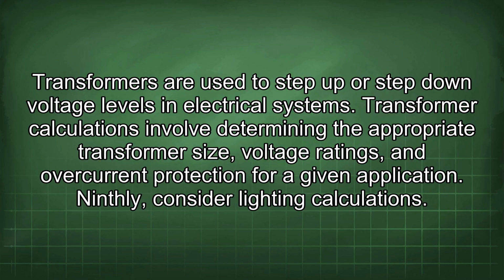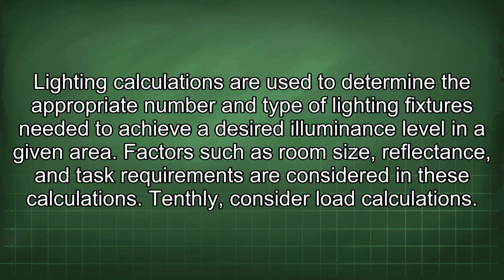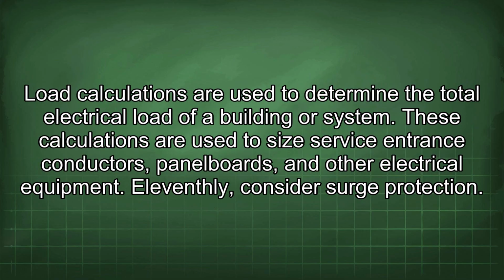Ninthly, consider lighting calculations. Lighting calculations are used to determine the appropriate number and type of lighting fixtures needed to achieve a desired illuminance level in a given area. Factors such as room size, reflectance, and task requirements are considered in these calculations. Tenthly, consider load calculations. Load calculations are used to determine the total electrical load of a building or system. These calculations are used to size service entrance conductors, panel boards, and other electrical equipment.